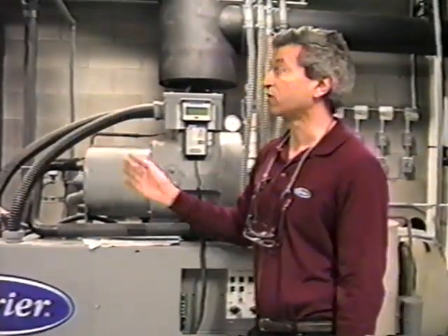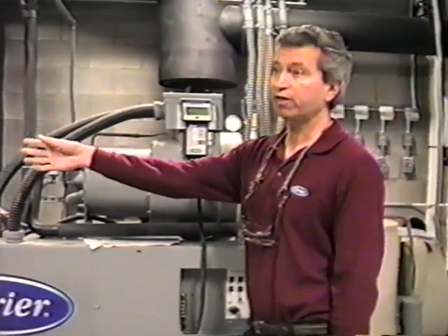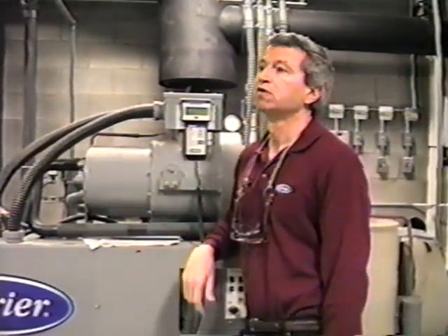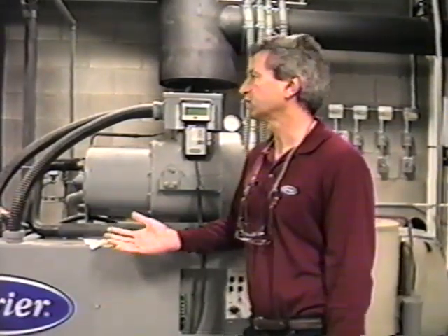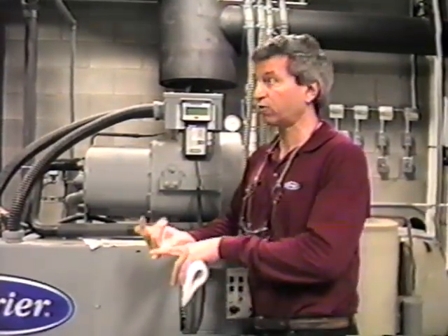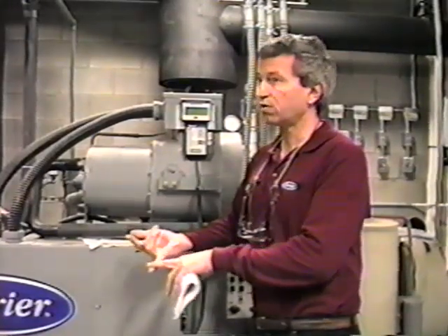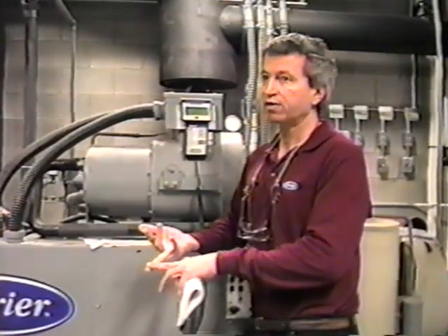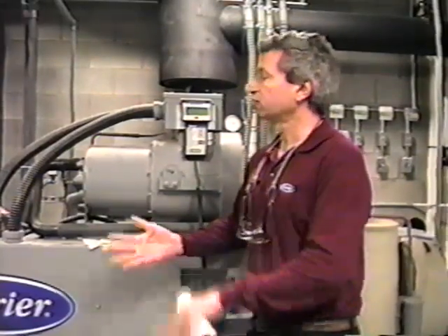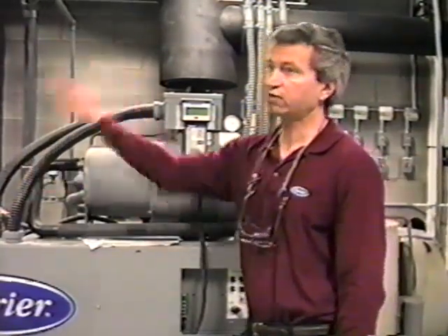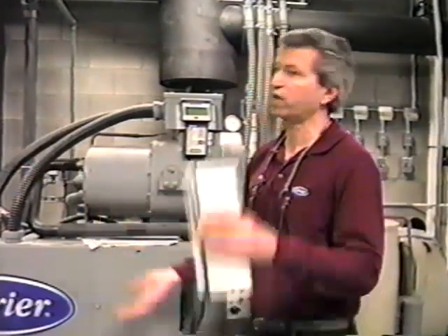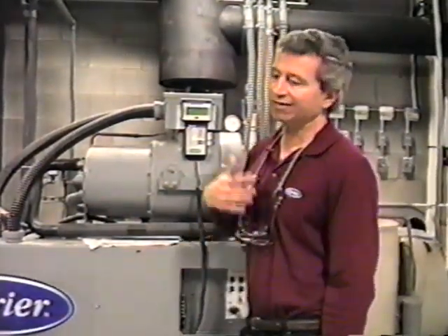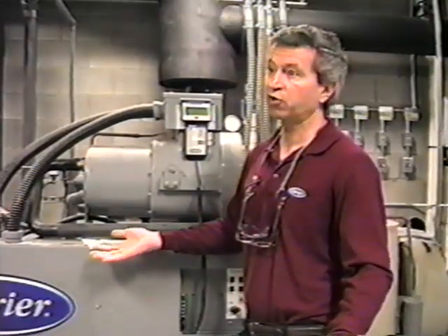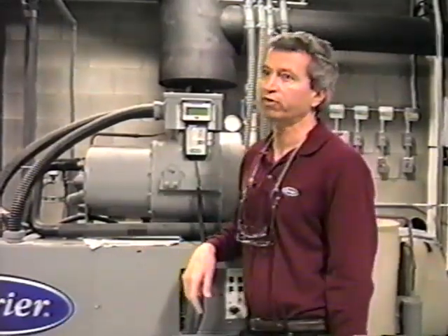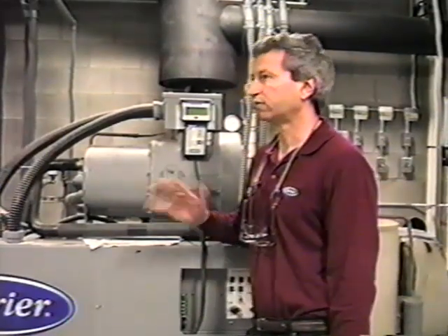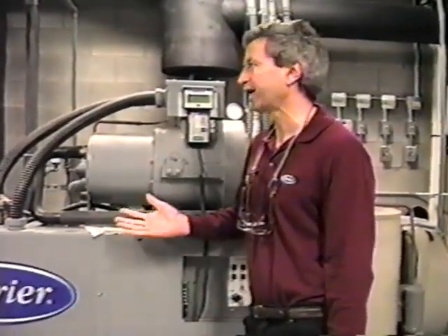There's an automatic lead-lag, so at any given time, the other circuit may start first versus this circuit. And the way it determines that is it looks at 1/4 the number of operating hours of that circuit along with the number of starts. And it adds those two together, and the circuit with the least number will be the next circuit to start. Okay, so it tries to balance things out. And again, we look at a start as being roughly 4 hours of operation as far as wear and tear on the motor. Okay, so that's why the processor uses that little formula to decide which circuit to start.